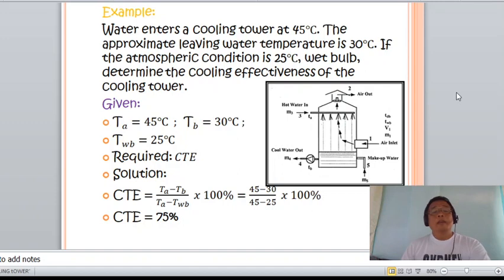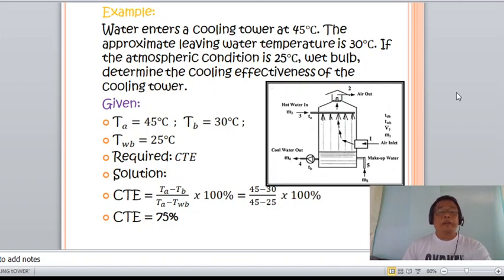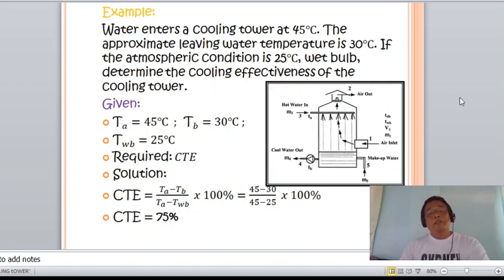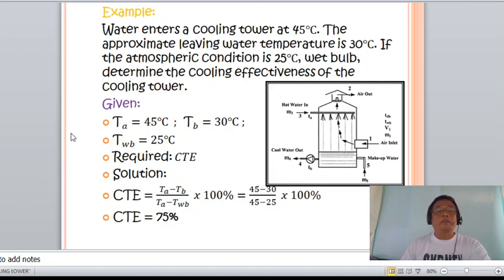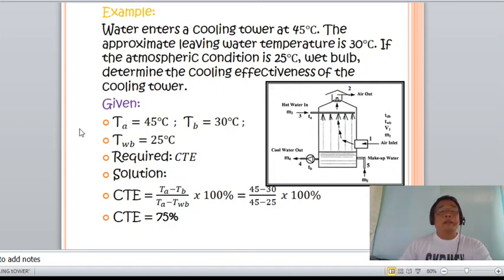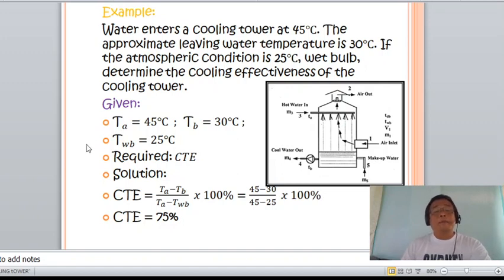Knowing that the cooling tower efficiency is equal to the actual range over the theoretical range — that is, the temperature of water entering the tower minus the temperature of water leaving the tower, divided by the temperature of water entering the tower minus the wet bulb temperature — multiplied by 100 percent. Substituting values: efficiency = (45 − 30) / (45 − 25) × 100%.